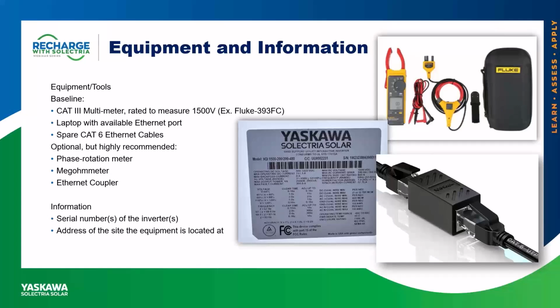So, equipment and information. The first thing we have listed here are baseline pieces of equipment. Those being a Cat 3 multimeter rated to measure 1500 volts, an example being the Fluke 393FC, a laptop with an available Ethernet port, and spare Cat 6 Ethernet cables. Items listed as the baseline are essential, providing the basic information and performing standard troubleshooting on XGI inverters.